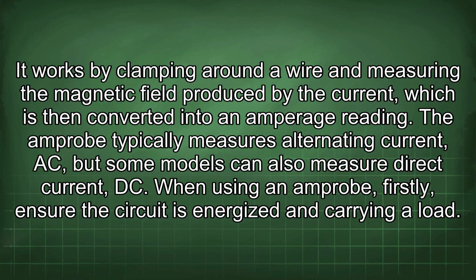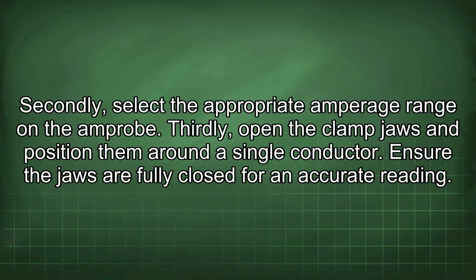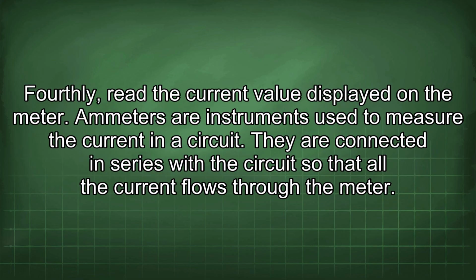When using an amprobe, firstly, ensure the circuit is energized and carrying a load. Secondly, select the appropriate amperage range on the amprobe. Thirdly, open the clamp jaws and position them around a single conductor. Ensure the jaws are fully closed for an accurate reading. Fourthly, read the current value displayed on the meter.